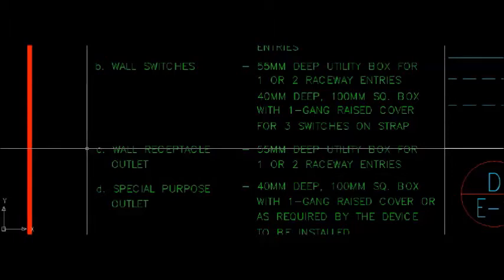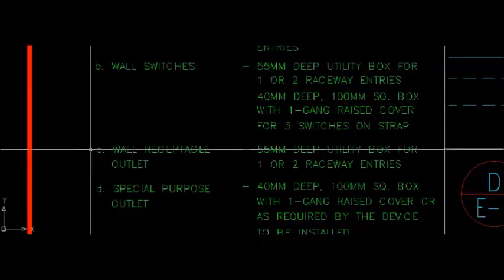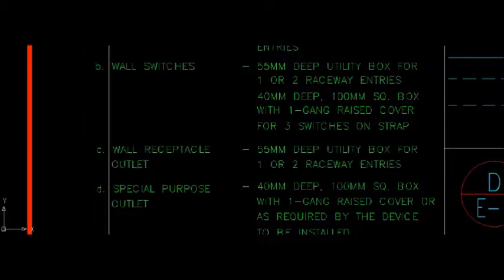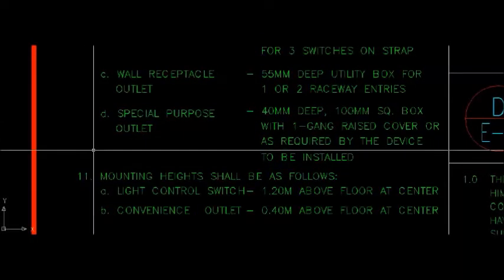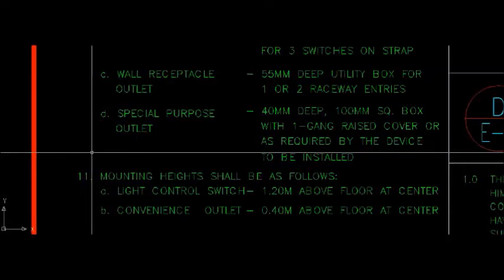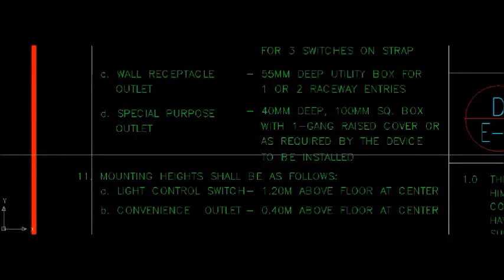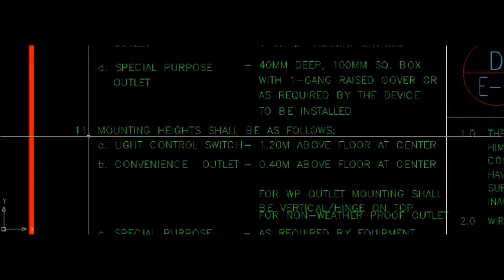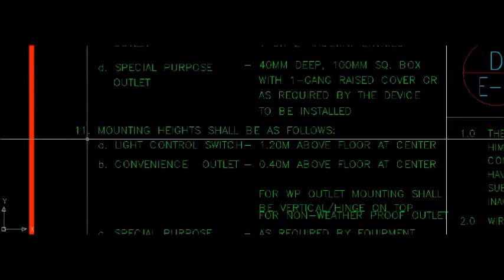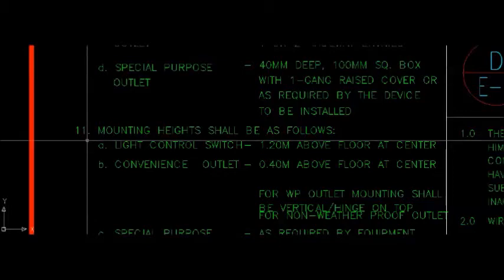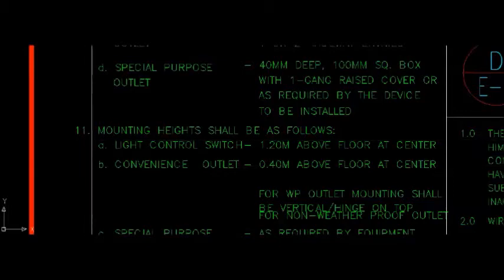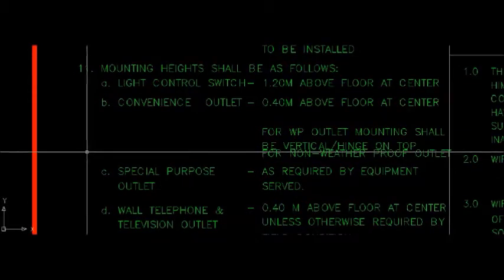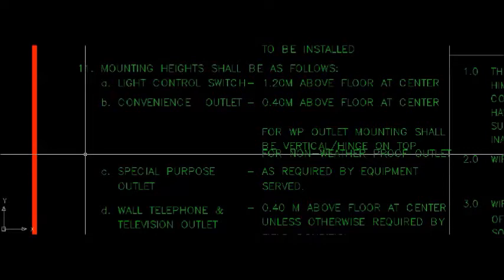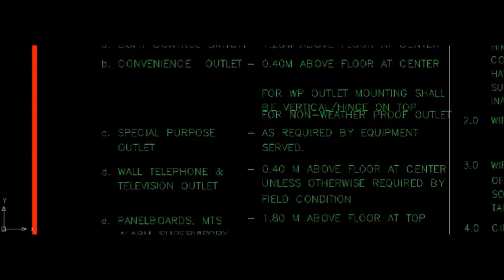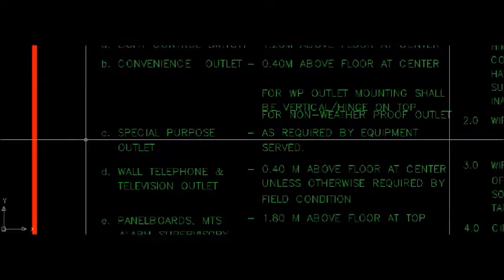40 mm deep, 100 mm square box with 1 gang raised cover for 3 switches on strap. Wall receptacle outlet, 55 mm deep utility box for 1 or 2 raceway entries. Special purpose outlet, 40 mm deep, 100 mm square box with 1 gang raised cover or as required by the device to be installed. Mounting heights shall be as follows. Light control switch, 1.20 meters above floor at center. Convenience outlet, 0.40 meters above floor at center.